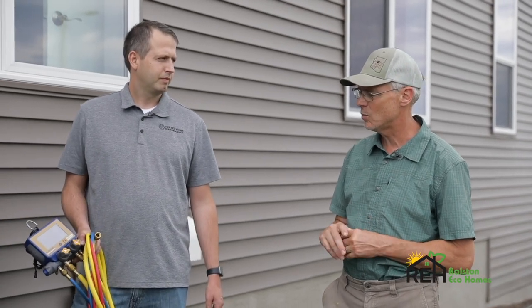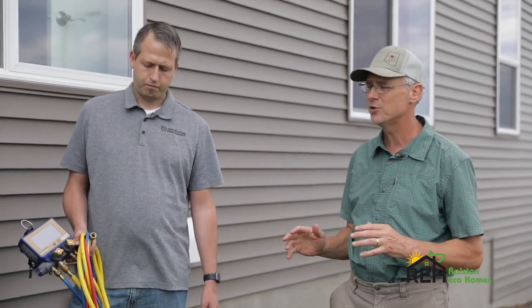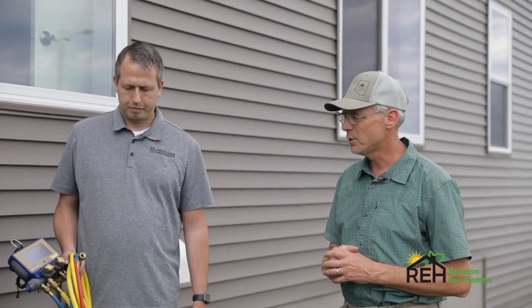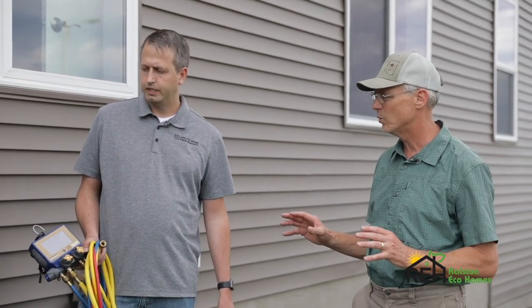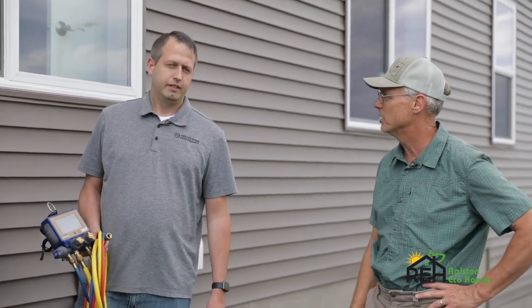Okay, we've got the air handler working the way we think it should work, and now we've gone throughout the house and balanced our registers by putting in dampers and getting those set up the way we want them. And then the third place that we're going to make sure that the system is working properly is outdoors here. We're going to work with the refrigerant. So what are you looking at? What are you going to measure out here on the refrigerant to make sure it's working properly?